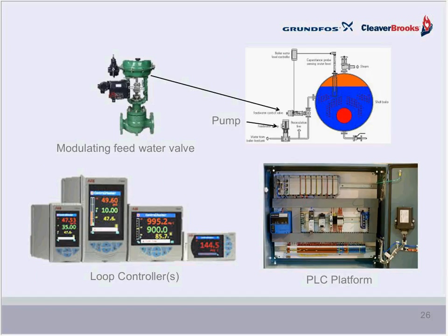Now, I just mentioned how this control sends both a digital signal for starting and stopping an on-off pump, or starting with initially a continuously operating pump. And it normally has two analog signals, let's say 4 to 20 milliamp, sending those signals to a loop controller or a PLC for the purpose of indicating level in the boiler and operating a modulating feed water valve. Now, looking at the pictorial drawing in the upper right corner of the screen, you see how the pump and the feed water valve are typically configured. And Jim will talk more about this a bit later.